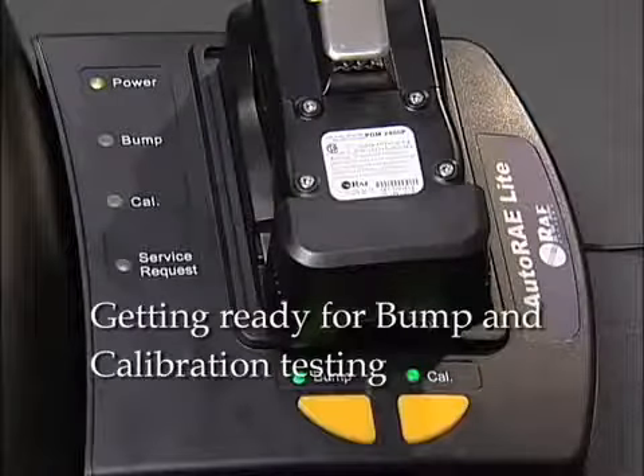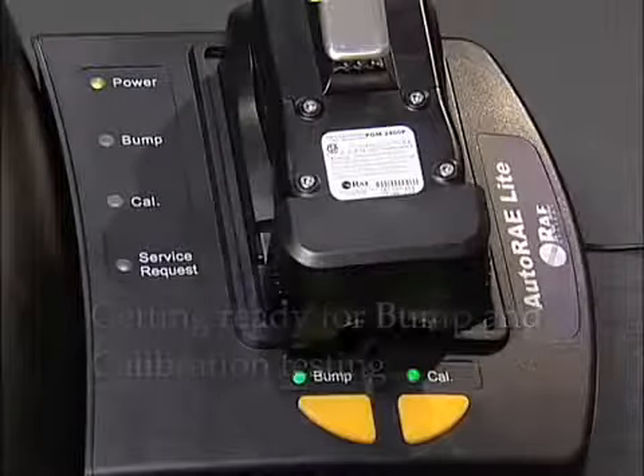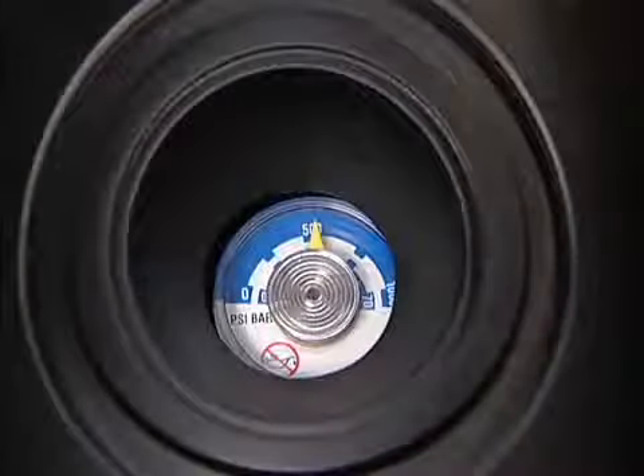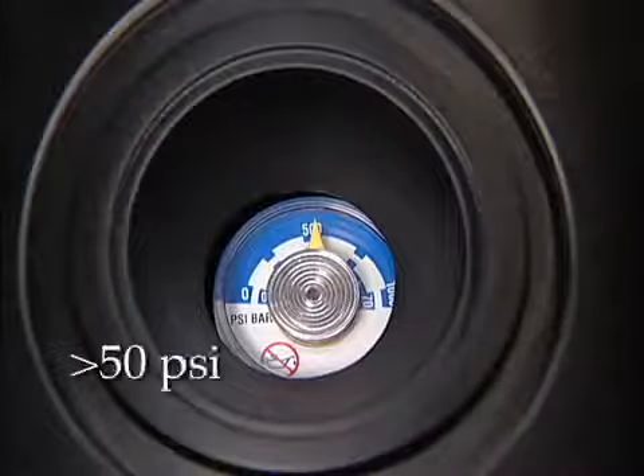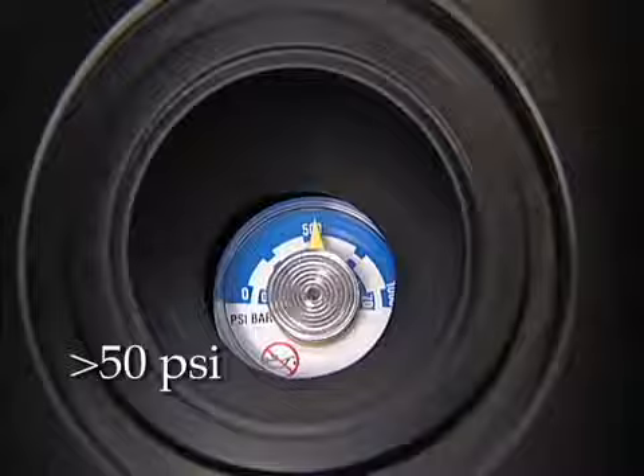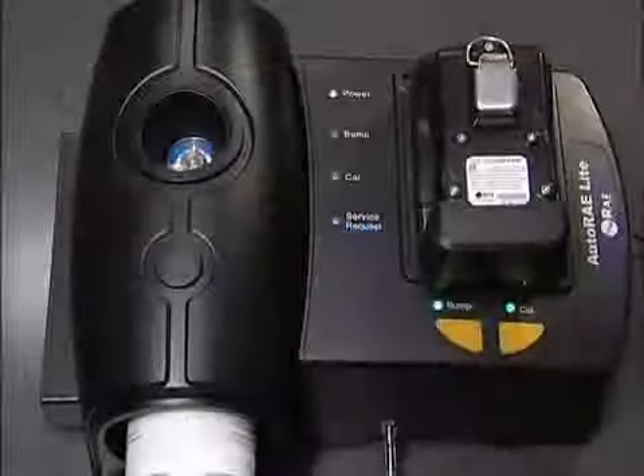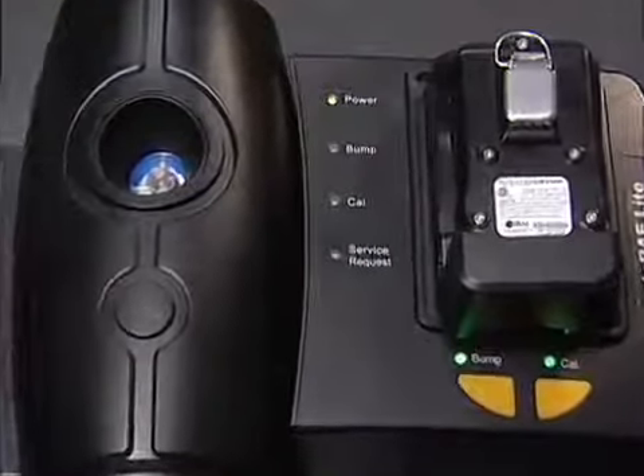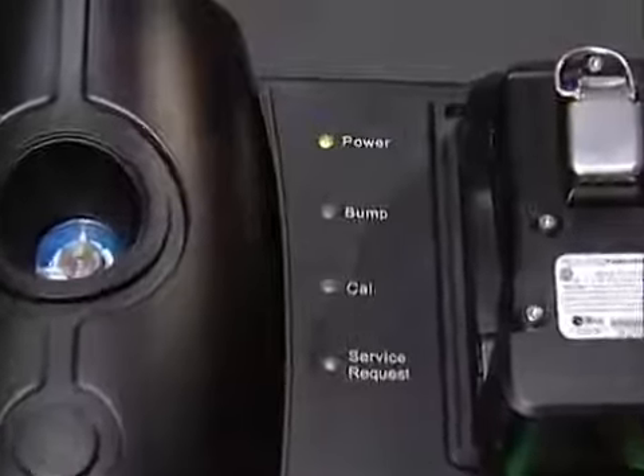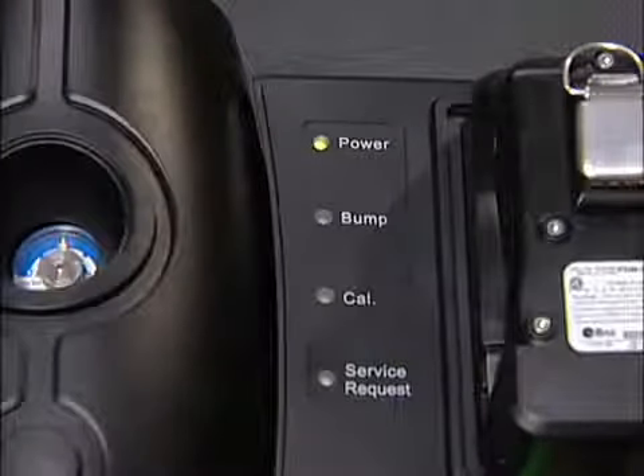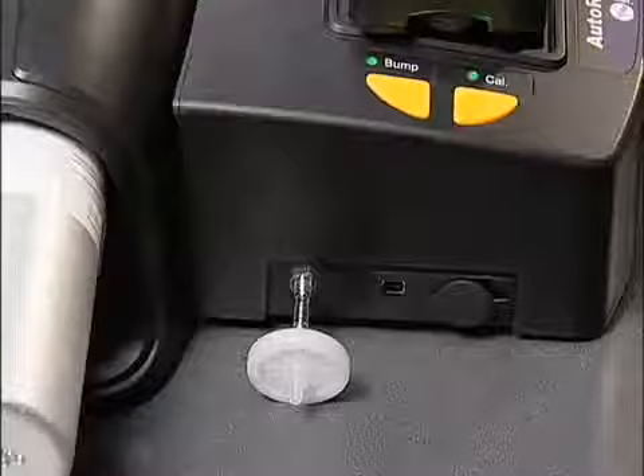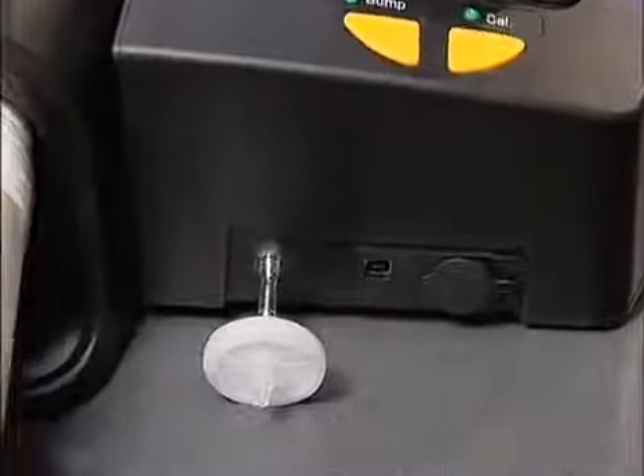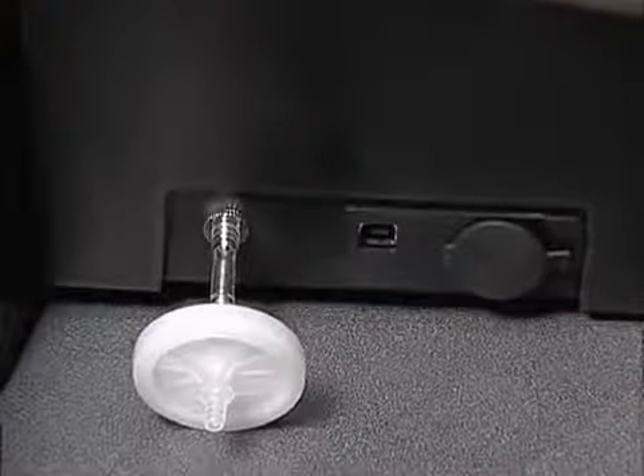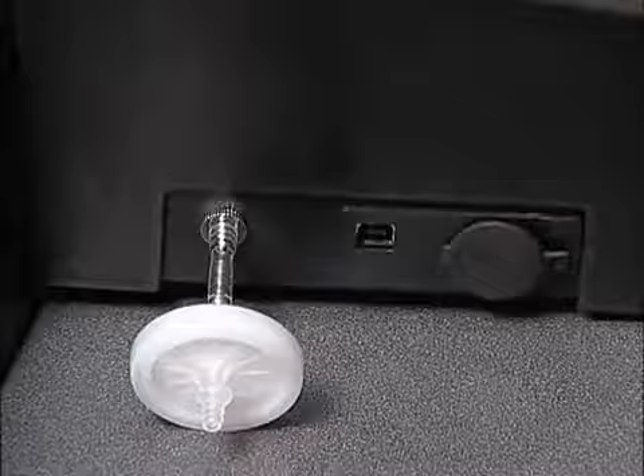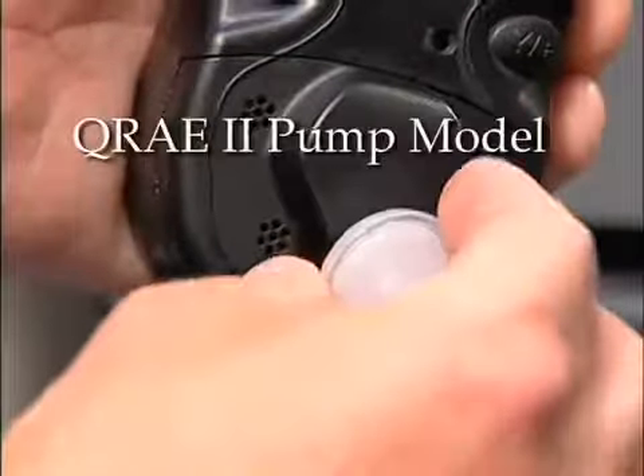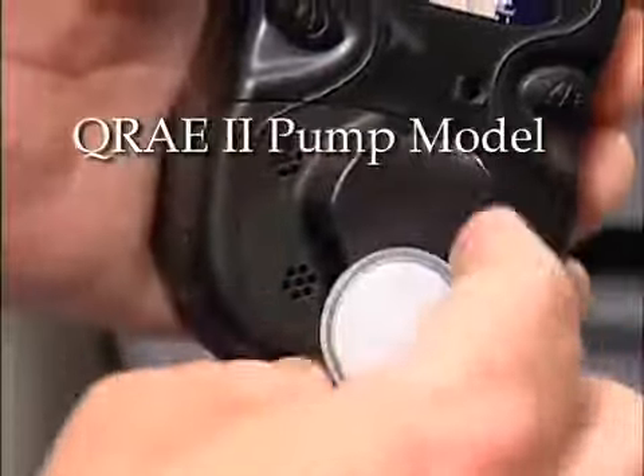Before using the AutoRAELite for QRAE II, perform the following checkout. Make sure the calibration gas cylinder is attached and that the pressure gauge reads more than 50 psi. If it is powered by an AC adapter instead of batteries, make sure the AC adapter is plugged into an outlet and the power LED is glowing green. Make sure the air inlet is not blocked and that a filter is attached. If the QRAE II is a pump model, make sure an external filter is attached to the unit.